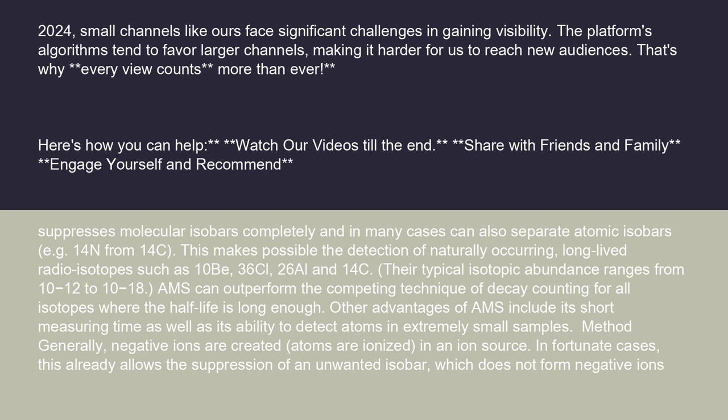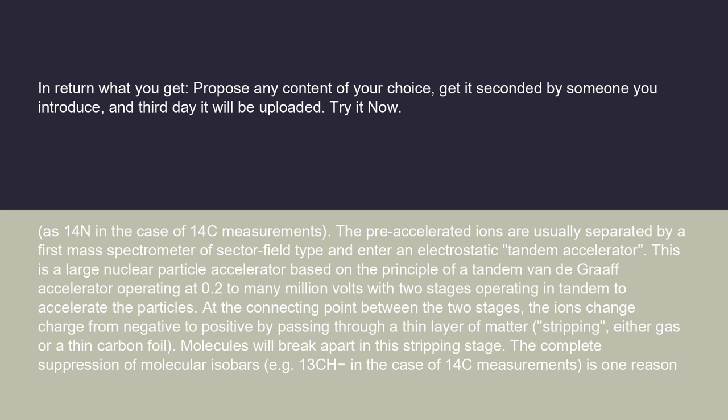Regarding the method generally: negative ions are created — atoms are ionized — in an ion source. In fortunate cases, this already allows the suppression of an unwanted isobar which does not form negative ions, such as 14N in the case of 14C measurements. The pre-accelerated ions are usually separated by a first mass spectrometer of sector field type.